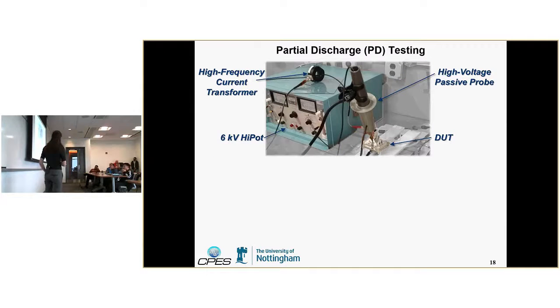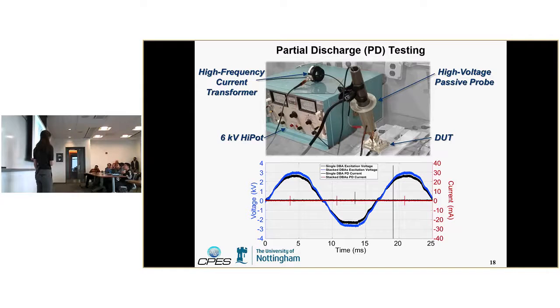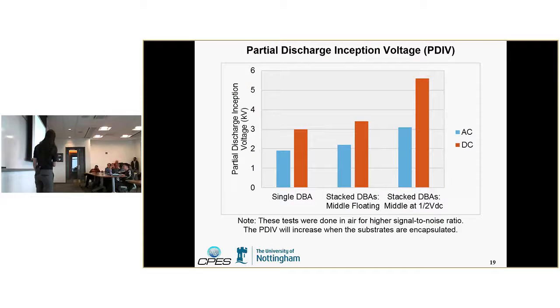And we also did partial discharge tests to verify this. So this is the setup. We've got a high pot tester, a high voltage probe, and we use a high frequency current transformer to measure the partial discharge signals. And this is an example waveform. This is with a line frequency AC excitation, and these little current spikes are the partial discharge events. And this is plotting those partial discharge inception voltages for 3 different cases.